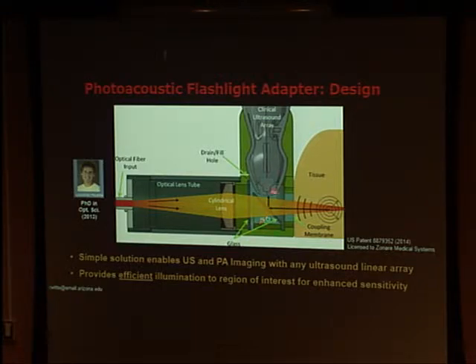This is a water-filled compartment for the acoustic coupling. We have what's called a Tegaderm, a thin film that touches the skin or the object you're imaging, providing coupling at the edge. The big difference from regular ultrasound imaging is that the probe is now perpendicular to how you'd normally hold it, so a radiologist wouldn't like that. We have ideas of how to correct that—we're certainly looking for partners in optical sciences to help solve this, to make it more upright rather than this perpendicular design.